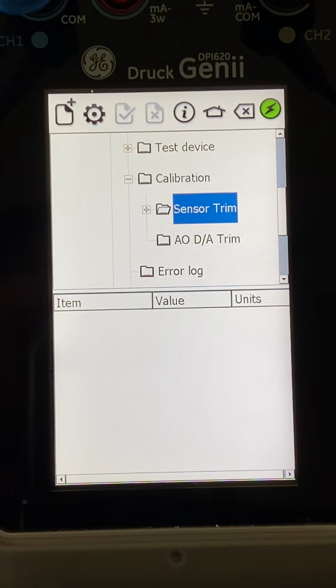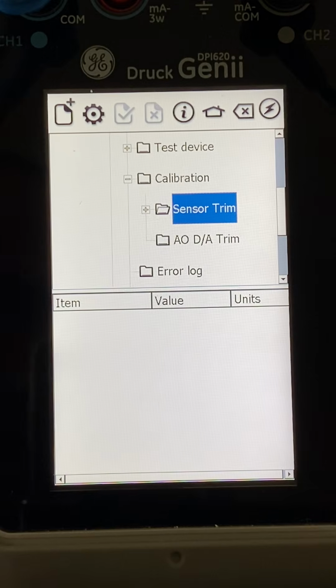Either I do it on keypad input, or I do it on actual from a calibrator. Doing that on actual from the calibrator will help you get the right compensation of the ambient temperature. So if the device is in a hot area or a relatively warm area, or if it's in a cold place, then I'll apply the actual 0, the actual 100, considering the atmosphere. So no need to do a compensation by calculation, then apply it by keypad input. You can simply utilize the calibrator function to do that in real time.